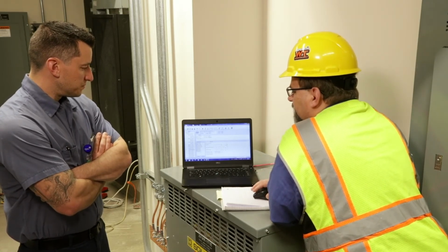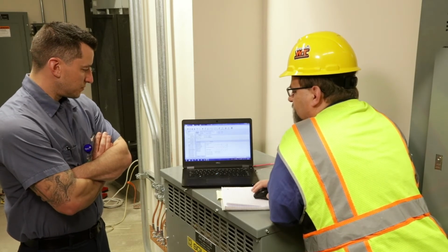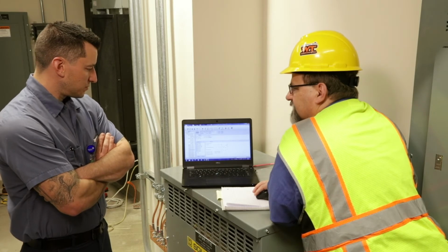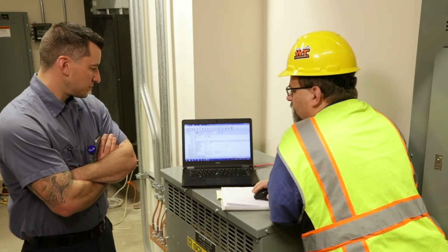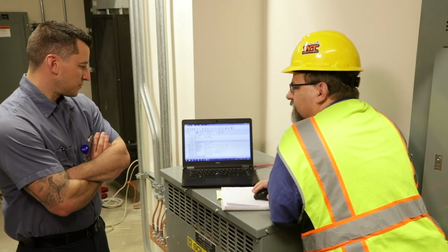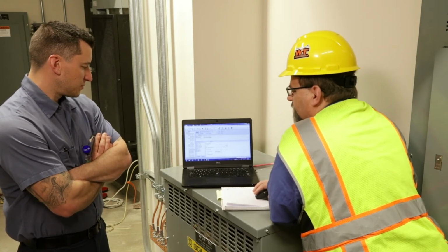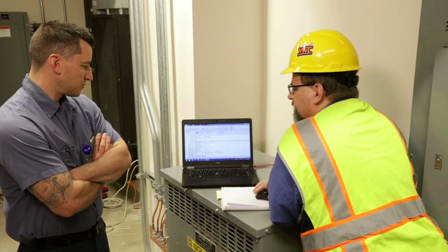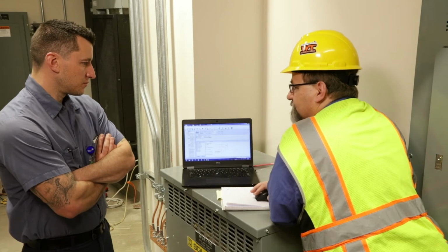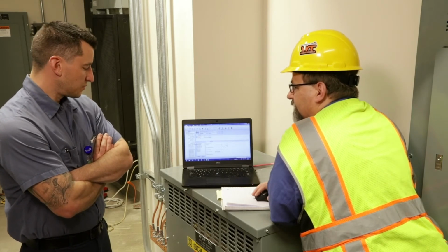If you take this sensor and take it to a conference room somewhere, this sensor is still going to try and talk to all 11 of these devices, which are essentially virtual loads, 1, 2, 3, right? The conference room might only have loads 1, 2, and 3, but this is still going to try and talk to 5 through 11, right? It's not going to make sense to the sensor. It's going to flash at you. It's still going to do what it's supposed to do for those loads 1, 2, and 3. You see what I'm saying?